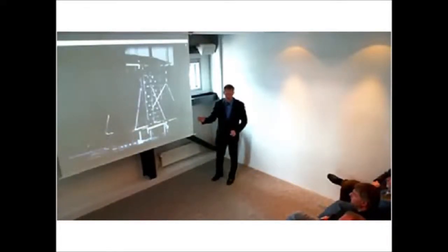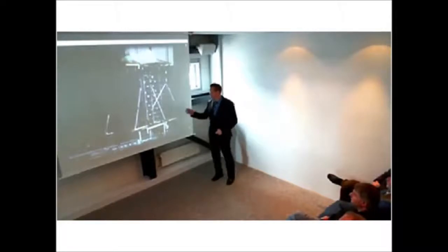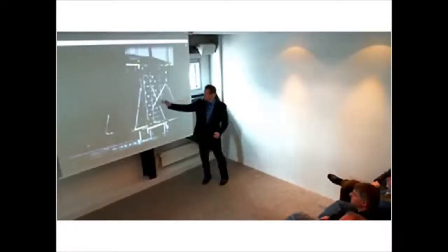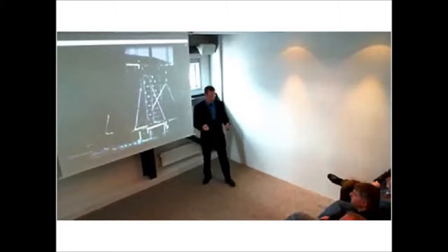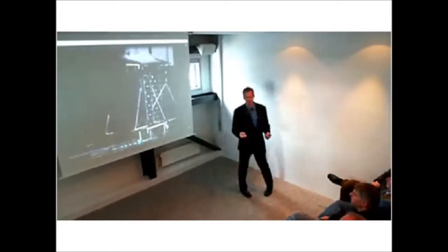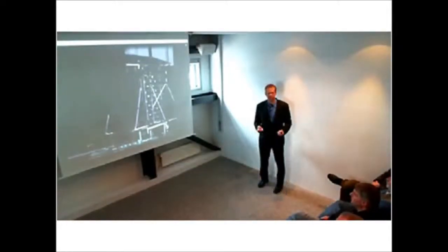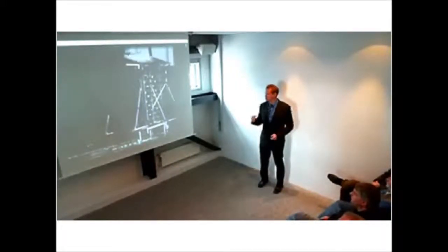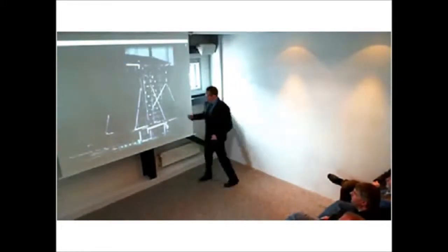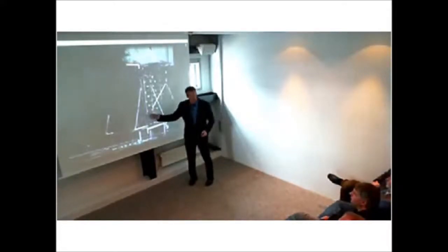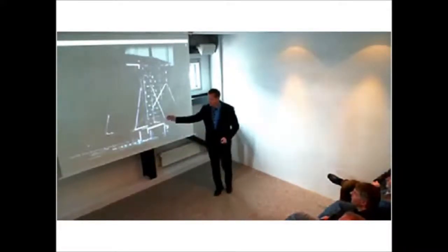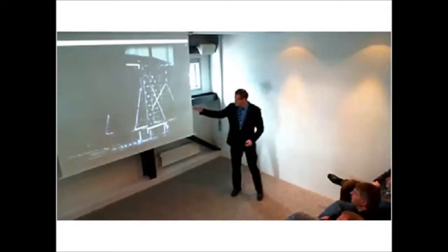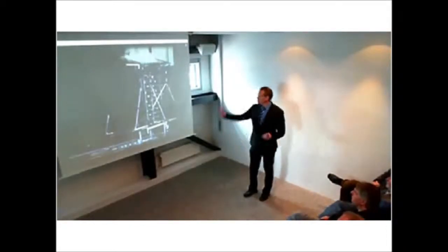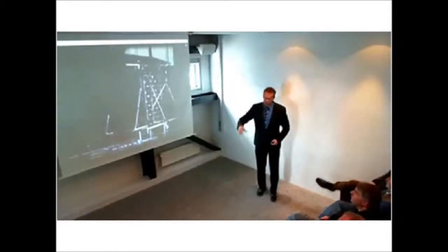This is just 1 second. 21 kiloamps. We have the door locked, and we have a fault inside the RMU, the switchgear, and a full short circuit for 1 second. And you can see by the arc, this is not with the arc suppressor. So everything is going to blow up here and go up in the roof. You see there, the roof is popping up.